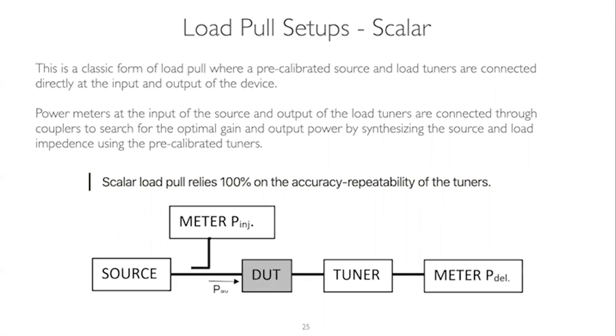The scalar one is really based on power measurements, on power meter measurements. So you have your device, and usually a passive tuner - you wouldn't have an active system for this. Basically, what you're doing is measuring the output power and input power by coupling it through a coupler on the input, or the same on the output, or just through an attenuator. What you're doing is cascading the different blocks to de-embed the power at the device plane.